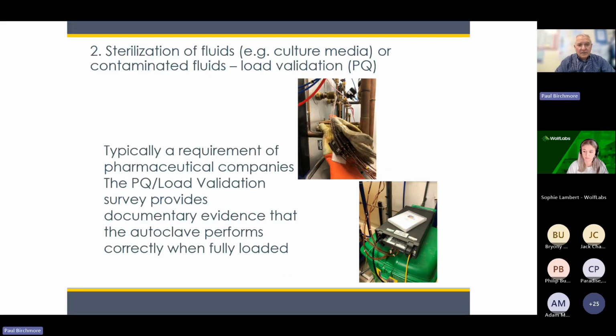And that's commonly the typical requirement of pharmaceutical companies, PQ load validation surveys, to provide that documentary evidence that the unit not only has completed the cycle, but the load has completed the cycle successfully as well. So there's a key word here, I'm sure you know this, but load validation is with a full load of the item, the sample itself. An autoclave that was being calibrated would be completely empty. So you do a calibration in the factory at the manufacturing stage. You might carry that out on site to prove that it had been delivered and installed correctly. It's part of your IQ, OQ really. And then you go from calibration empty to load validation full. And that's your difference between calibration and validation.